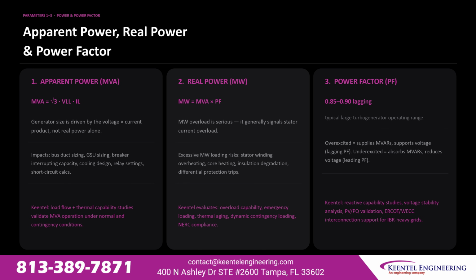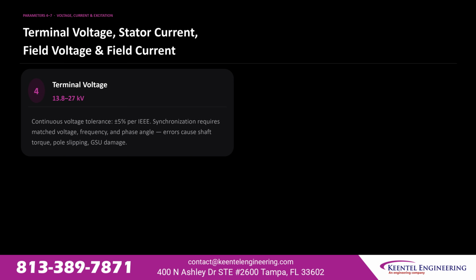Overexcited operation supplies reactive power and supports voltage. Underexcited operation absorbs reactive power and reduces voltage. Keentel performs reactive capability studies, voltage stability analysis, and ERCOT and WECC interconnection support for inverter-based resource-heavy grids. Terminal voltage typically runs 13.8 to 27 kilovolts with continuous tolerance of plus or minus 5% per IEEE standards. Synchronization requires matched voltage, frequency, and phase angle. Errors cause shaft torque, pole slipping, and transformer damage.